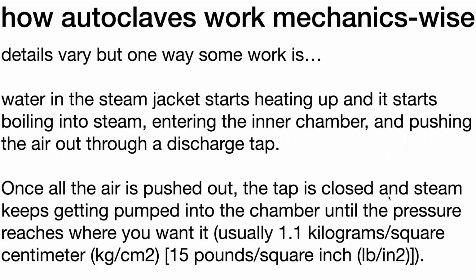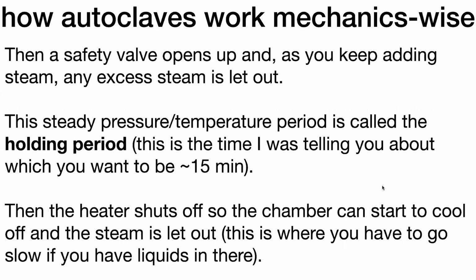As it starts entering the chamber, in the beginning, if you're using one of those gravity systems, it's going to be pushing the air out through that discharge trap. And once all the air is pushed out, that trap is going to get closed. And now when you keep pumping in the steam, the pressure is going to build. And once it gets to where you want, typically about 15 pounds per square inch or 1.1 kilograms per square centimeter, you're going to start your major sterilization.